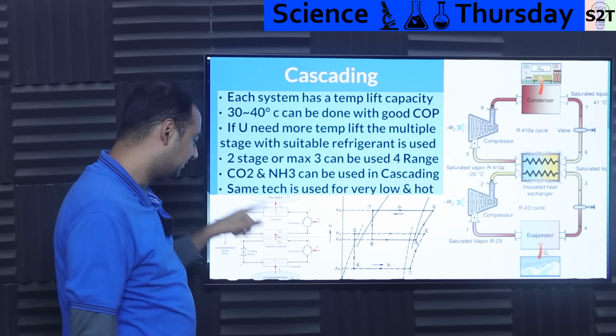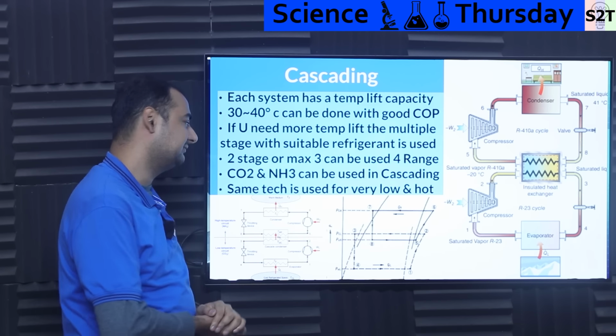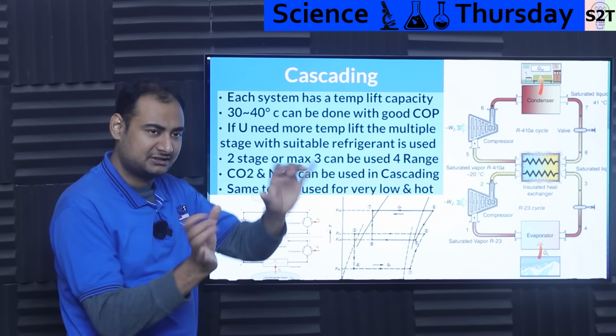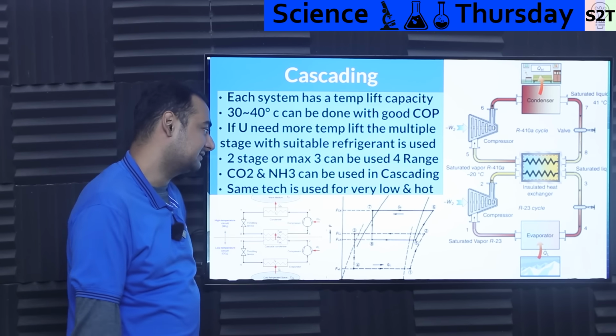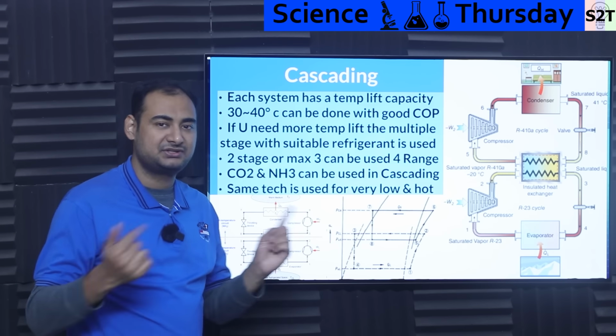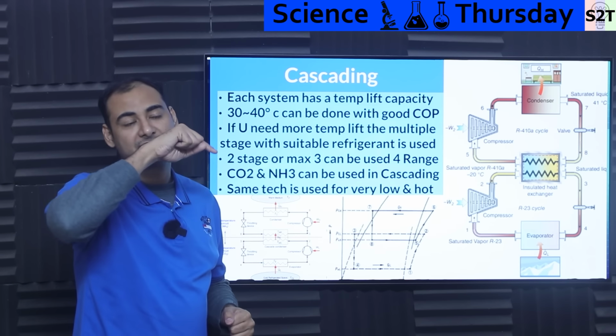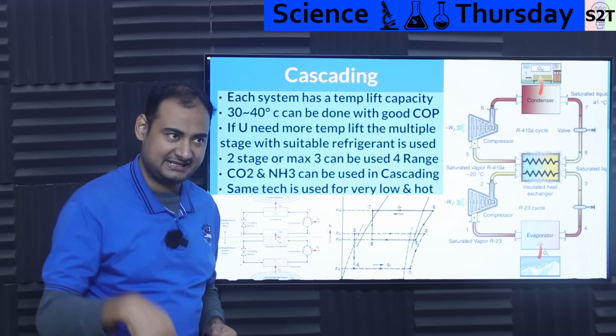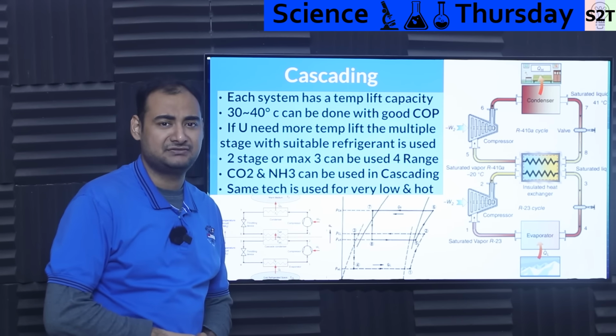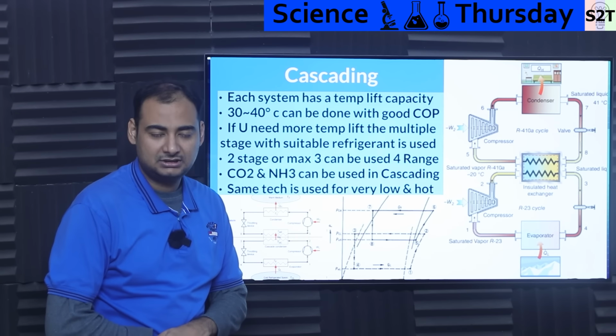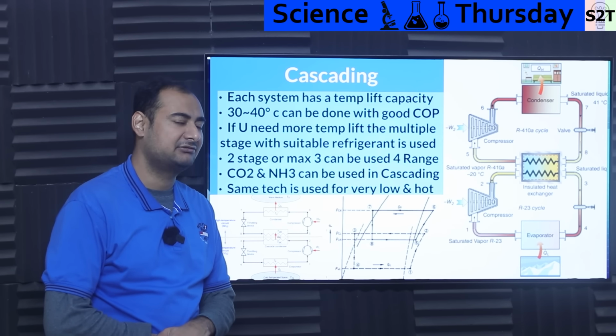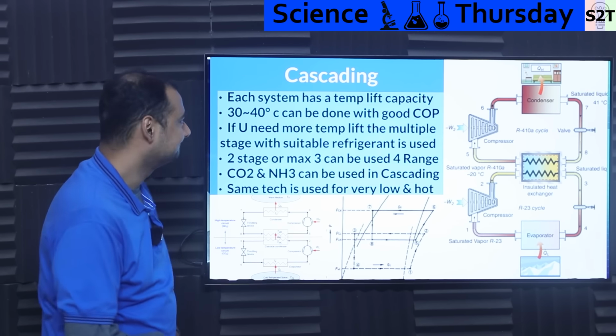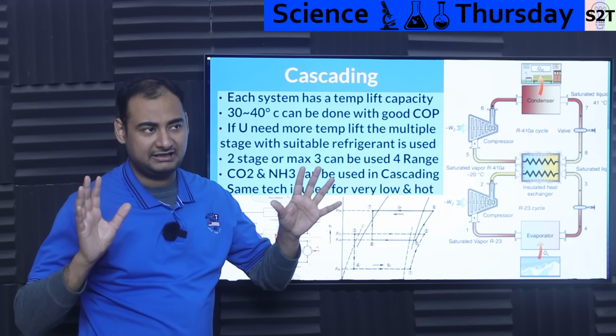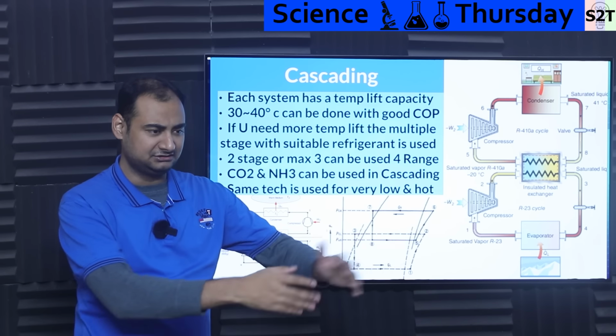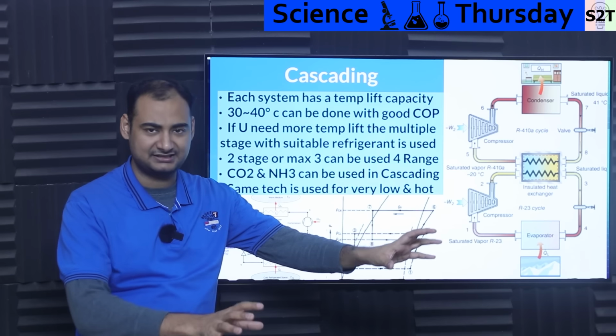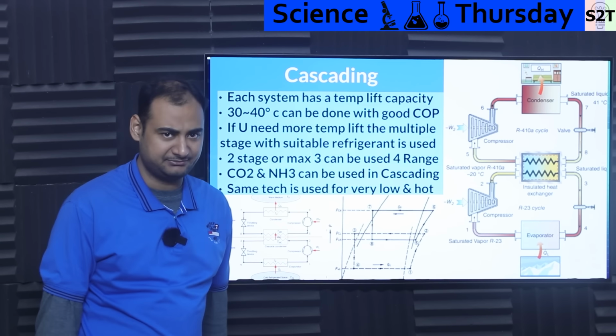CO2 and ammonia are commonly used in one loop and another loop. That gives a very good cascading effect when you want a lot of temperature range. This exact same philosophy works both ways, whether you want to lift the temperature or depress it. You want minus 70 degrees for antibiotics or RNA vaccines, which require very low temperature. Same thing. That's the cascading part. You'll most likely never hear us stop at just one loop. It will always be loop one, loop two. That's how we get very high temperature.